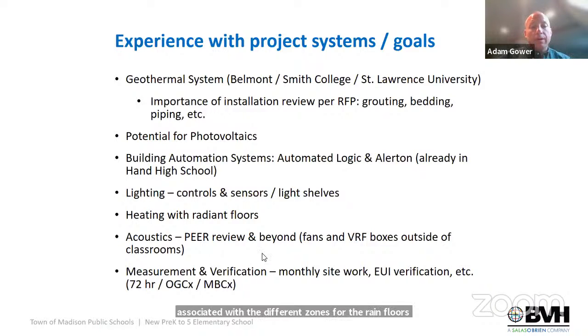Acoustics was a concern in the ed spec, part of your goals, so we'll catch those concerns early on in the peer review, and keep it in our forefront for the remainder of the project. We'd recommend not having fans in the classroom above the ceiling—fan coil units or other terminal equipment, as well as VRF mixing boxes of refrigerant—kept outside the classrooms. We've had issues in the past when they're designed to be in the ceiling of classrooms, where they make more noise than you'd think.